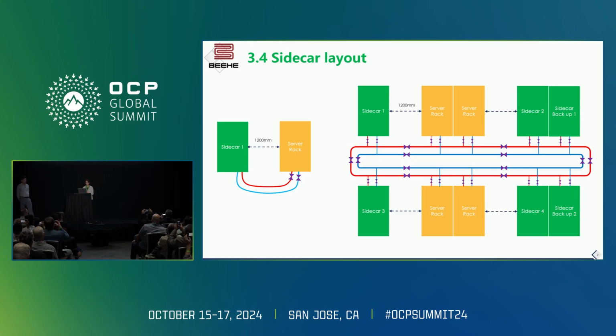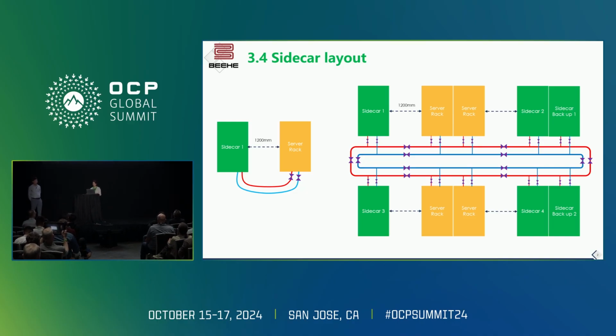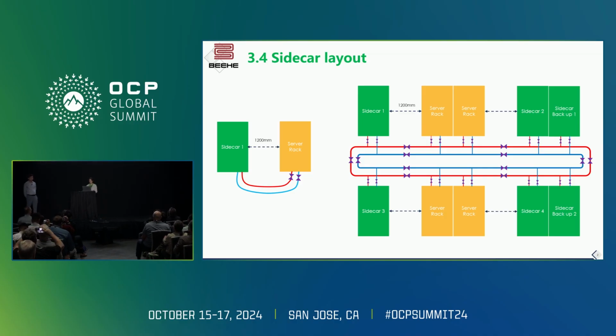One thing to call out is that for all of our CDU configurations, we apply N+1 redundancy, so we always have two CDUs in operation and one backup. If any one of them fails, the backup automatically takes over. For sidecar units, we also apply a safety distance between the sidecar and the server rack, to prevent the airflow intake from interfering with each other.